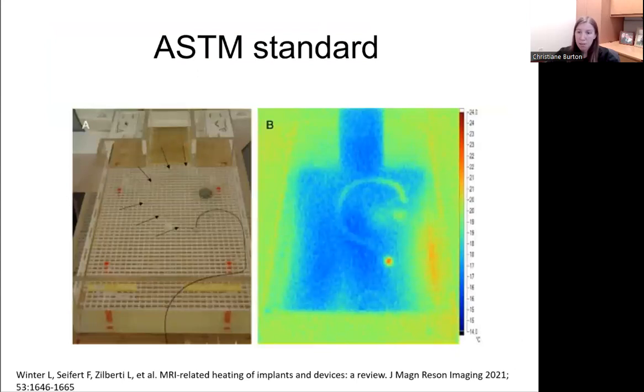This is an illustration of the ASTM standard. The image on the left shows a procedure that is described using a saline-based gel-filled phantom of approximately the same dimensions of the body part where the implant is located. The gel is doped to have electrical and thermal properties similar to the human tissue. Temperature change in and around the implant is recorded following 15 minutes of continuous RF exposure to a SAR of at least 2 watts per kilogram averaged over the volume of the phantom.